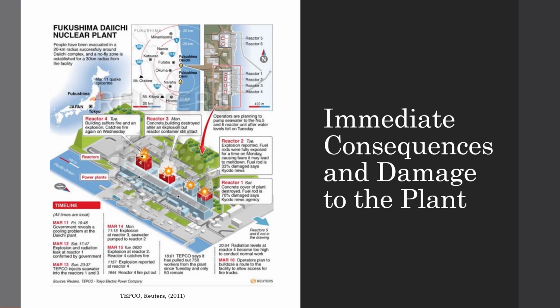Immediately upon the earthquake's occurrence, the Fukushima plant went into an automatic shutdown for the 3 online reactors. At the time, the operating reactors were those of units 1, 2, and 3. The other reactor units at Fukushima Daiichi were already shut down for fueling and maintenance. The next issue faced by the plant was a dilemma of decay heat removal, which the equipment is dependent on electrical power. There was damage to on-site switchyard equipment, off-site substation equipment, and the power lines supplying off-site AC power to the plant. This led to a loss of all off-site electrical power. Emergency diesel generators, or EDGs, automatically kicked on to successfully restore on-site power.